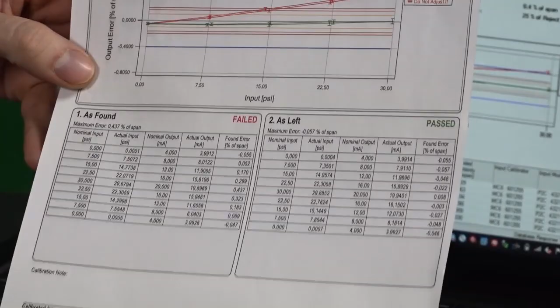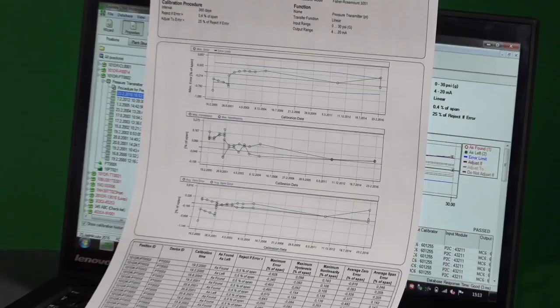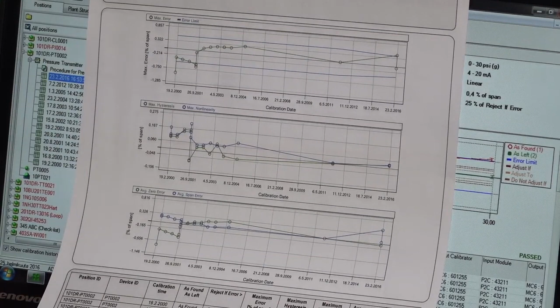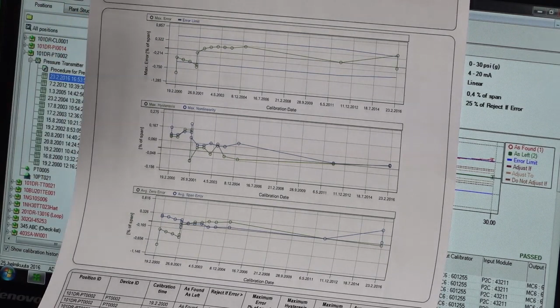One of the most important benefits of using CMX is the ability to reduce cost. One way of doing it is by using history trend. All it is is a set of different data from across the history of that instrument. So you can actually see right now that this instrument had about 10 calibrations done throughout the history. Some of them failed, outside of the blue lines, some of them passed. But you can actually start making conscious decisions based on a history trend. That could mean that you increase or reduce your calibration interval. You can also determine the quality of the particular instrument based on that. It's a very useful feature.